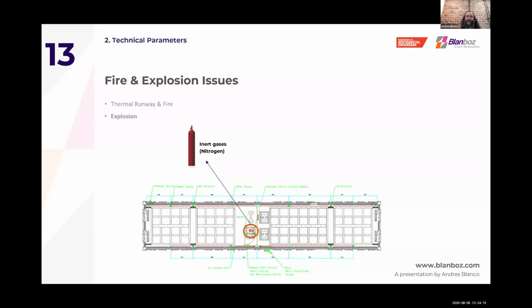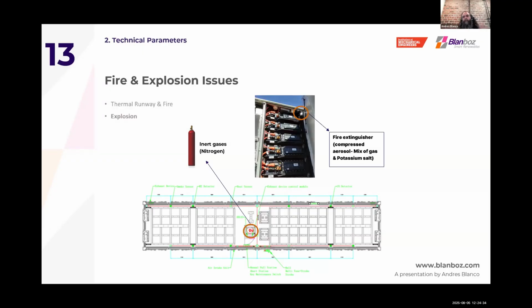Back in the day, we used to have inert gases or nitrogen, and you have to remember that these battery containers are quite airtight, so the system can be highly pressurized very quickly. And if you add on top of this your combustible gases, it can be a ticking bomb. And nowadays, you will see more often the compressed aerosol, which is a mix of gas and potassium salts to reduce the concentration of oxygen within the combustible gases. And you can also see either forced ventilation or vents that allow natural ventilation, trying to release those combustible gases to the atmosphere.